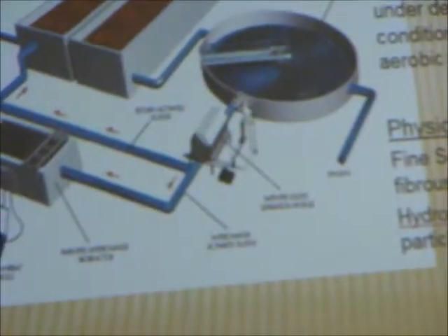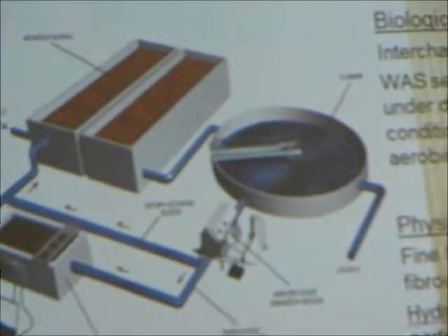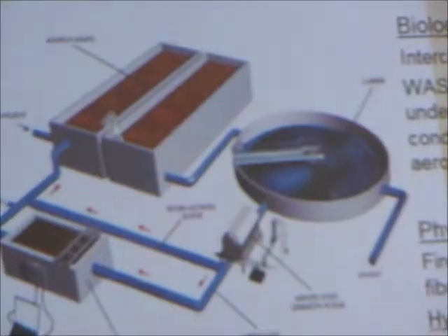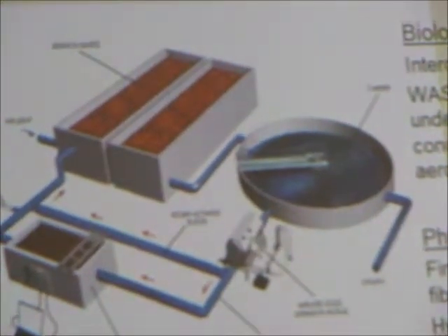You pump your mixed liquor into the screen, over the screen, the clear mixed liquor drains back into your aeration system, and the rags and the trash material is separated, stays on the other side, and it drops into a press. It's dewatered and pressed into a dumpster. We are up here, 2 IBRs. We see the aeration basin. It's going to the clarifiers, the effluent comes to your UV for disinfection, and out to the river.